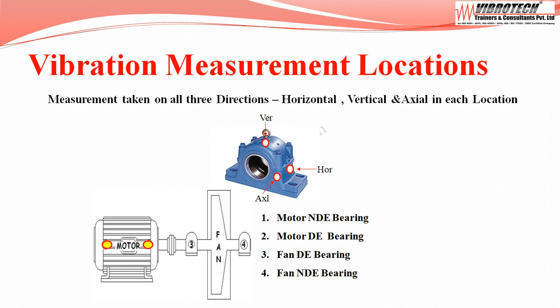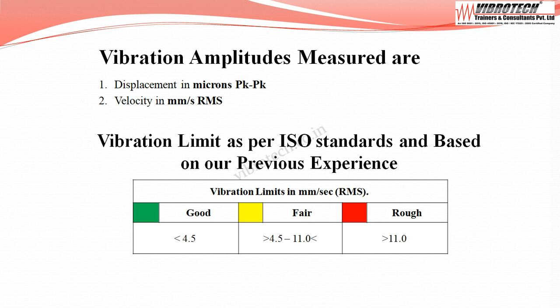Now onto the vibration limits. As per ISO standard and with our previous experience, when the velocity falls below 4.5 mm per second RMS, it is considered as good. When the velocity falls between 4.5 to 11.0 mm per second RMS, it is considered as fair. And when the velocity falls above 11.0 mm per second RMS, it is considered to be rough.